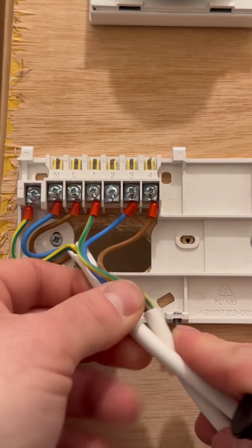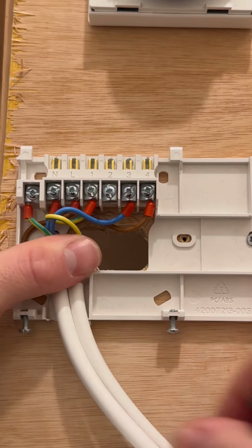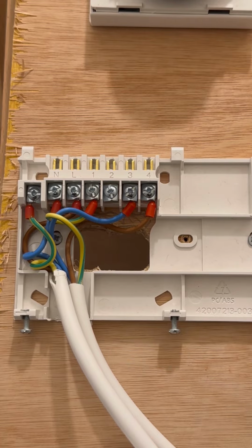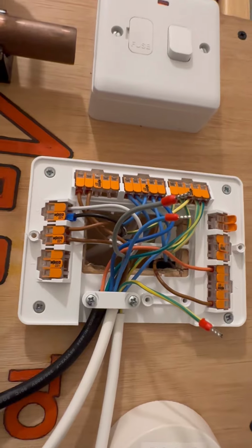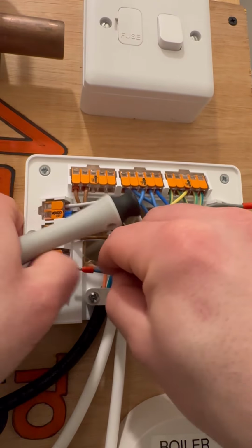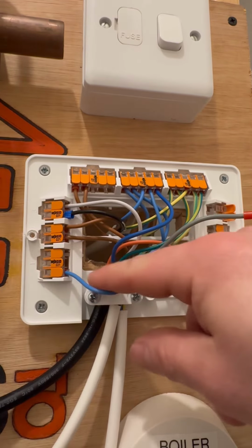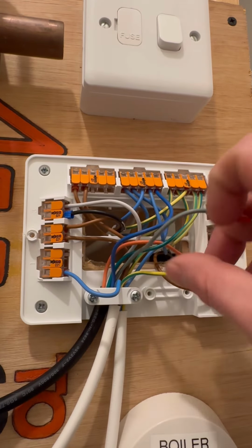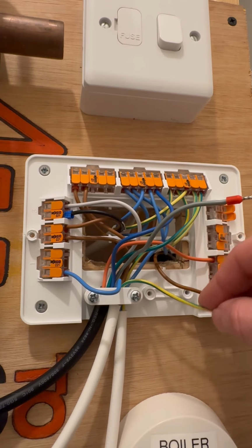So that's basically the programmer all wired, like that. So hot water on goes down there, and then it goes to the cylinder stat. But we have to go via the 10-way. Right, hot water on. I'm going to pop over here actually, like that. Blue. So just forget the colours for now. That should have some red tape on it or sleeving, because it's now a switch live, same with this. This is coming from the programmer, this one was hot water off.